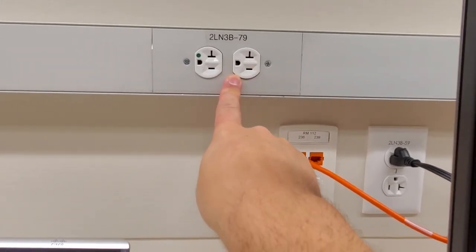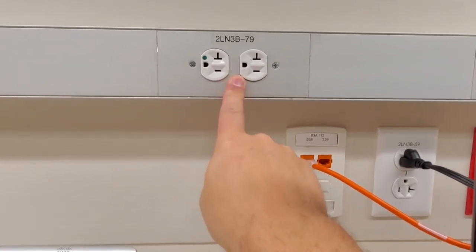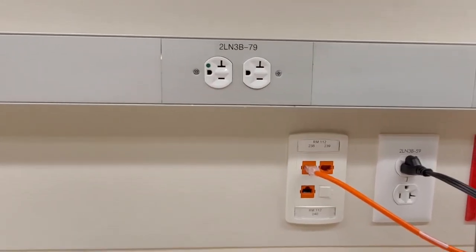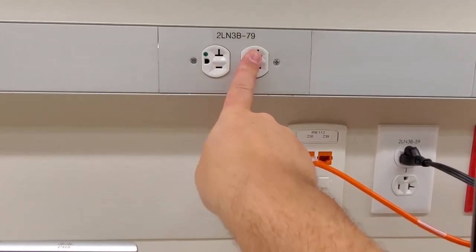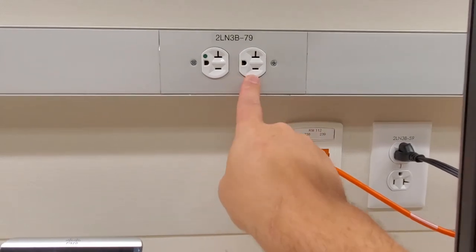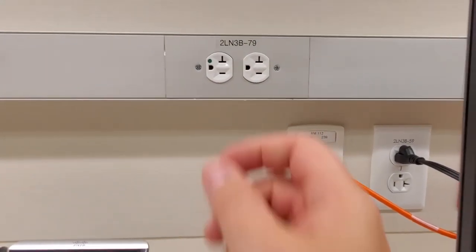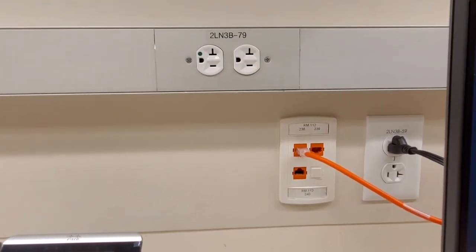In other words, you'll have a similar situation to what you might find in old houses where with old houses you'll have aluminum wiring and you'll have to go through the terminals and constantly tighten them back down, especially when there's extreme temperature changes because the wire, aluminum, will expand and contract at a different rate than the screws. So you'll get actually a loose terminal and you'll get arcing sparks back behind your electrical outlet.